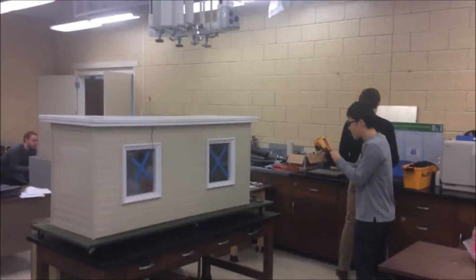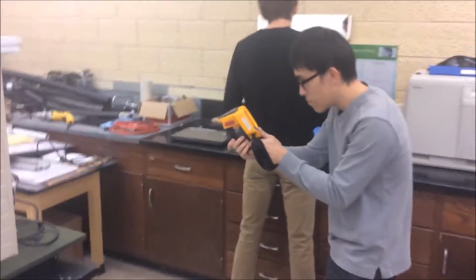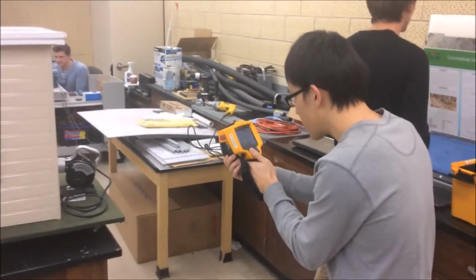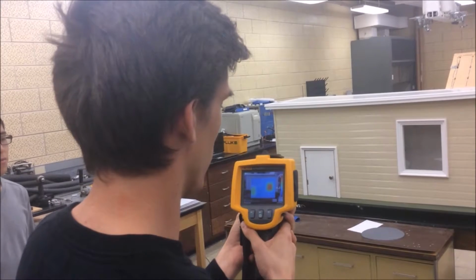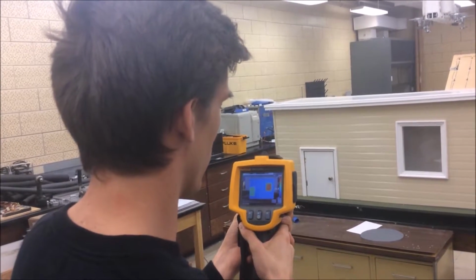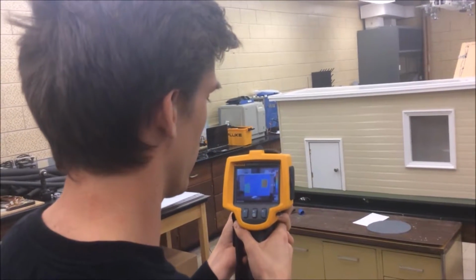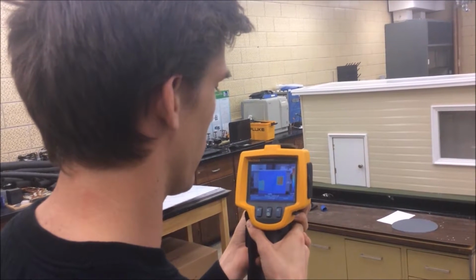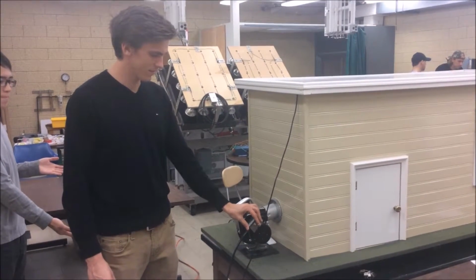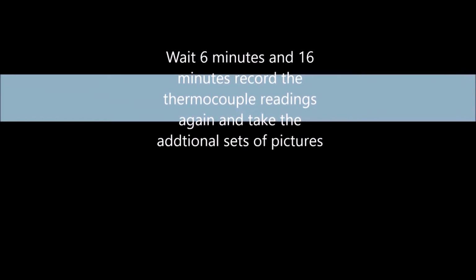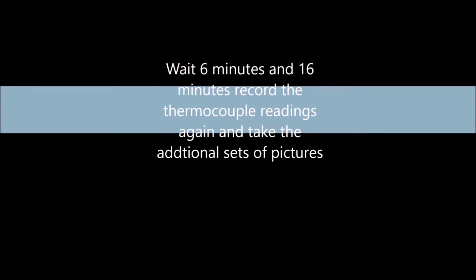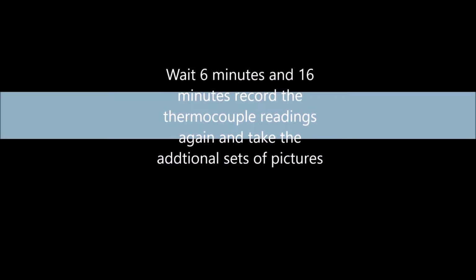One feature of interest might be the blower that will be heating the house. It is crucial in all of these images you are taking to adjust the focus. In post-processing, focus cannot be adjusted. After these images are taken, switch on the heat pump. After this, we will wait 6 minutes and then record the thermocouple readings and retake the thermal images. Do this again for a 3rd time after 16 minutes.